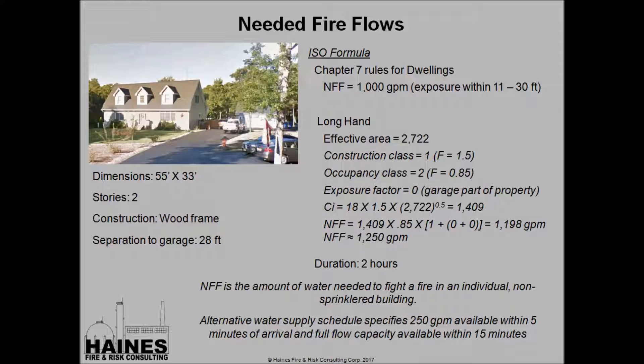The needed fire flow under ISO is the amount of water needed to fight a fire in an individual non-sprinkler building. The schedule assumes continuous water supply, but the alternative schedule looks for a two-hour duration for tanker shuttles and similar operations. The alternative water supply schedule specifies 250 GPM be available within five minutes of arrival, with flow capacity reaching its maximum within 15 minutes of the first piece of equipment arriving on scene.